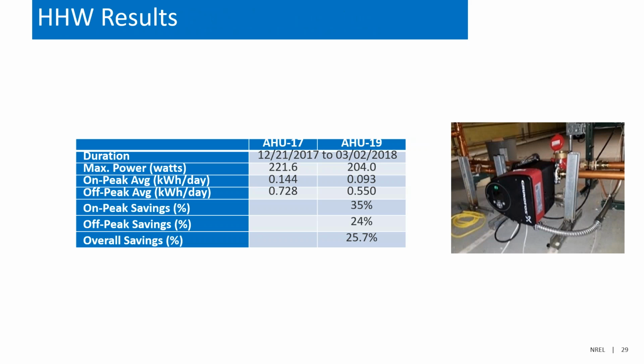So the energy savings that we got out of this one are substantially lower than the other one. I think the primary driver for that is if you look at AHU 17 versus 19, the max power, essentially the new market standard pump by this manufacturer is much more efficient than an older pump that would be sitting in there operating from 10 or 15 years ago. And so instead of seeing a 40 to 70% reduction in peak power, we're only seeing about a 7% improvement.